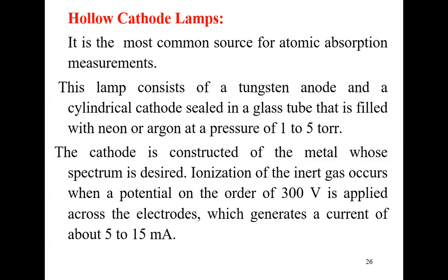Usually you will see the current marked on the lamp. You don't want to operate at that very high current for a newer lamp. You start at low current, and if it degrades, then you increase it a little, right? And you will see what's going to happen. After being sputtered, you'll see some black stuff on the glass because of the bombardment of those gases on the walls of the quartz tube.